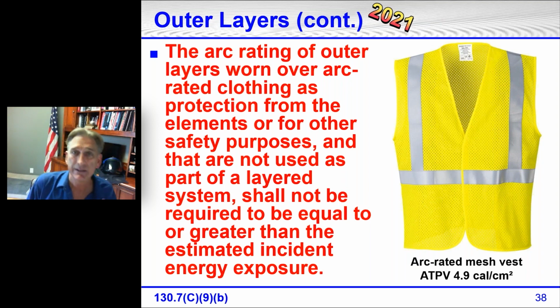All right, so what this means, anything that you wear on the outside has to be arc rated, yes, absolutely, but it does not have to equal or exceed the arc rating of the piece of equipment that you're in front of. For example, I've got a label on a piece of equipment that is 8 calorie. I've got a regular shirt on that is 8.7. All right, my shirt is good.